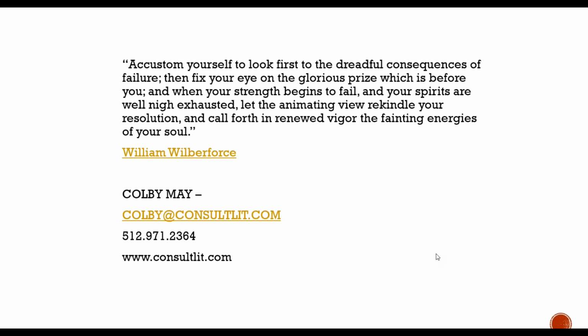Domestic hot water tanks, I'd even mention that. If you have an electric domestic hot water tank, if you think about it, you're maintaining 120 to 140 degree water 24 hours a day, 365 days a year, just to provide hot water for Sunday mornings. So I highly encourage time clocks if you can, because that would save on the life of the equipment, and it would save energy dollars. Right, so don't run them when you don't need them. Turn the temperature down if you don't really need that hot of a water.